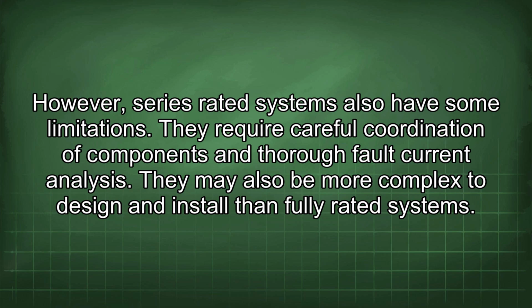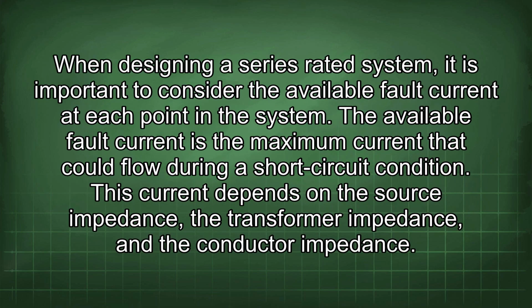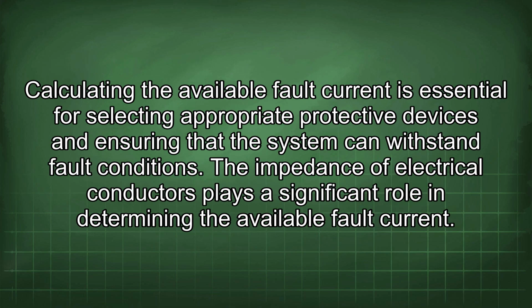They may also be more complex to design and install than fully rated systems. When designing a series-rated system, it is important to consider the available fault current at each point in the system. The available fault current is the maximum current that could flow during a short-circuit condition. This current depends on the source impedance, the transformer impedance, and the conductor impedance.